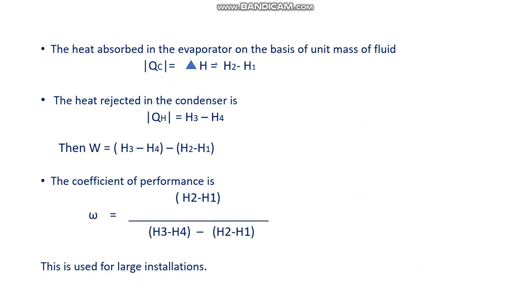The heat rejected in the condenser is qh = h3 − h4. From this, the work done is w = qh − qc = (h3 − h4) − (h2 − h1). The coefficient of performance is COP = ω = qc / w = (h2 − h1) / [(h3 − h4) − (h2 − h1)].